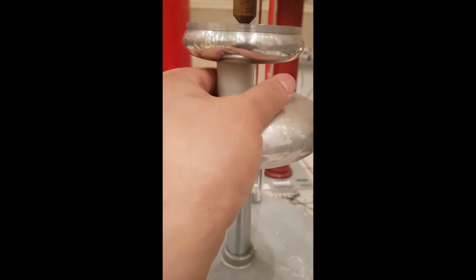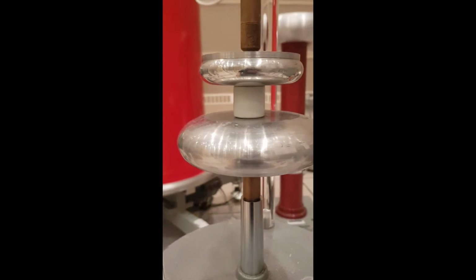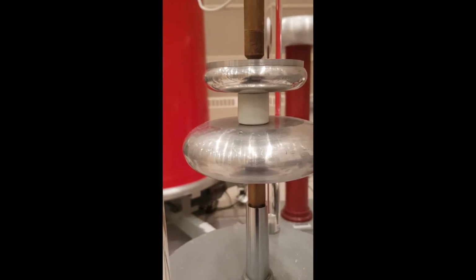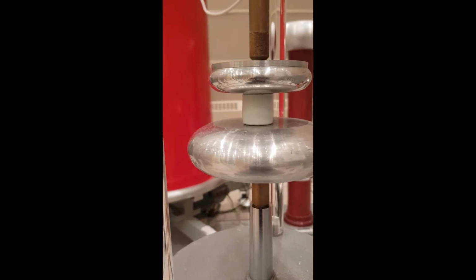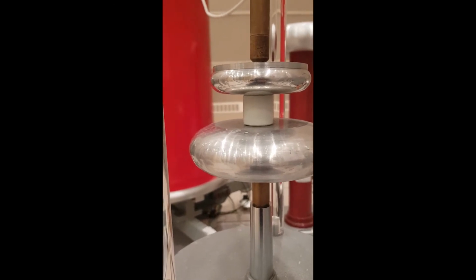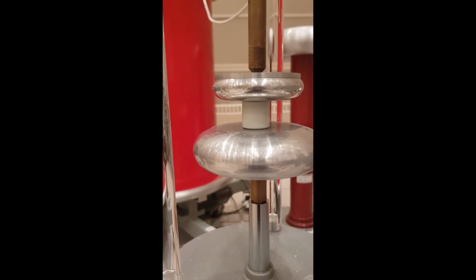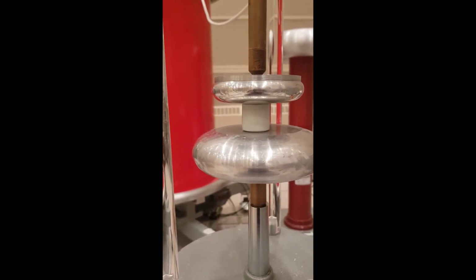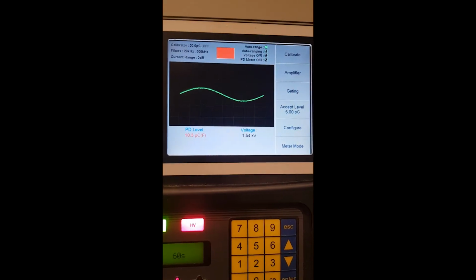Okay, and this parallel electrode will ensure that we will have a uniform electric field. So if there is any discharge, it will be coming from the void which is inside the insulation system. So now what I will do, I will go and apply high voltage, and we look to the PD pattern and see how the PD from a void looks like.